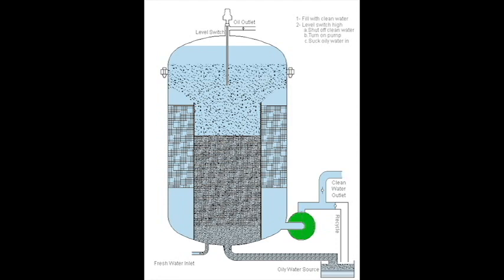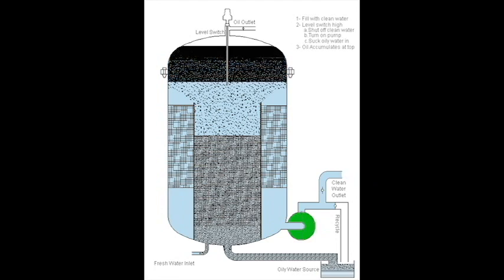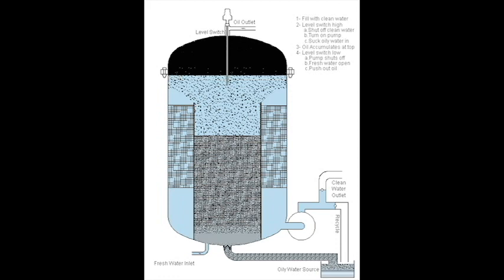Now the valves are closed and the process pump is turned on again, beginning to suck the oily water into the system. The oil again accumulates at the top of the vessel until the water level reaches the low set point again.